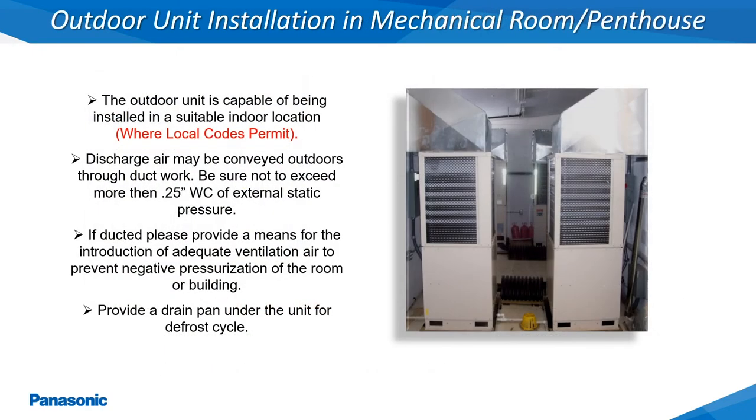The ECOi VRF outdoor units can also be installed into an indoor environment such as a penthouse or mechanical room where local building codes permit this type of installation. Once installed in this type of application, adequate makeup air must be supplied, calculated based on the number of outdoor units being installed.